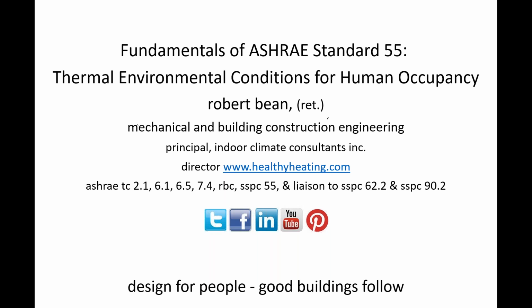Okay, another question from Alwinson Matthew. He's asking for the slide that showed the desired airspeed velocities. What standard is based on? Oh, so again, within ASHRAE Standard 55, there is a whole section on airspeeds. And so it looks at what is the person wearing, what are they doing, and what is the dry bulb temperature. And so it's actually a combination of those four elements that you can actually manipulate the airspeed. So as the person increases their metabolic rate by doing more higher level activity, less clothing, warmer air temperature, you can increase the airspeed. So the standard actually will do that.